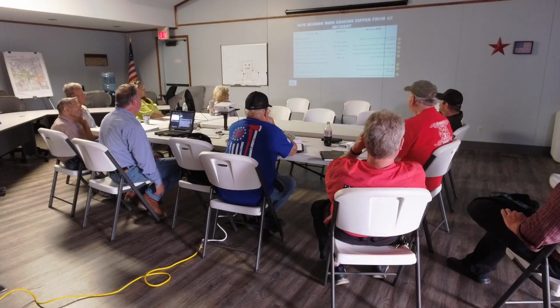So out of that came these standards you've been hearing about, including UL 1973, which is specific to the battery cell, UL 9540, NFPA 55, and NFPA 855.